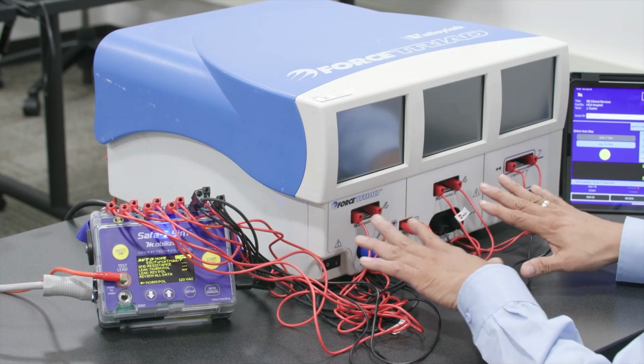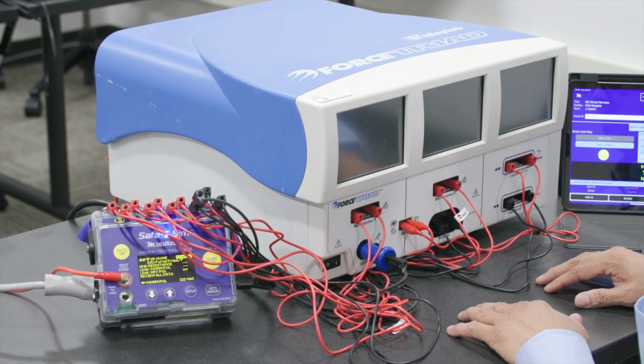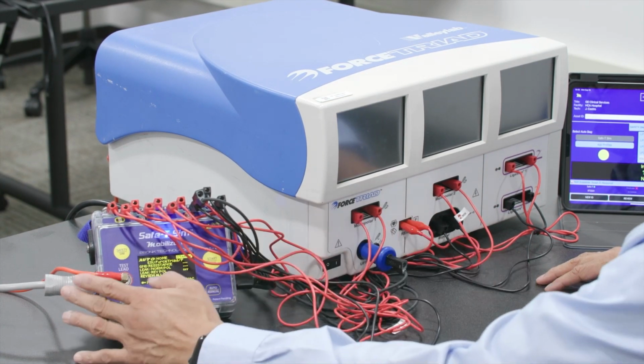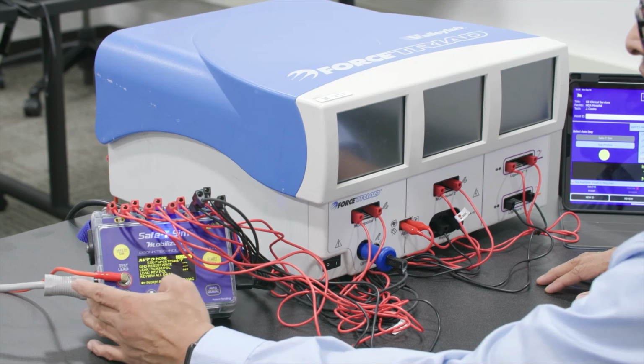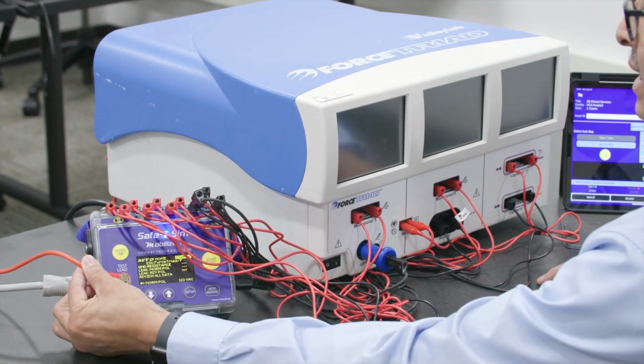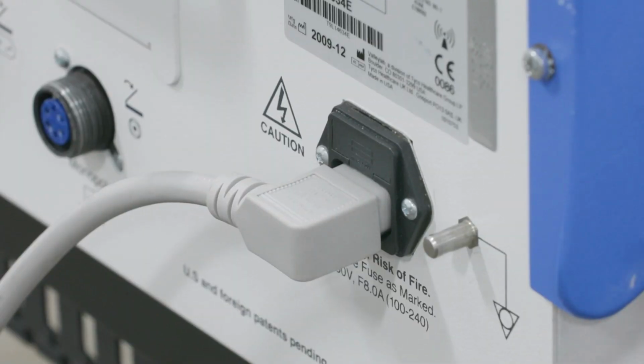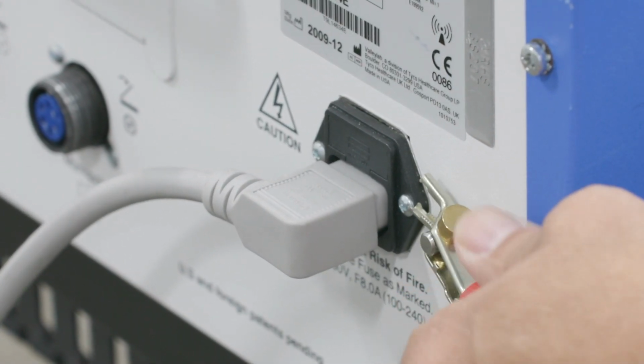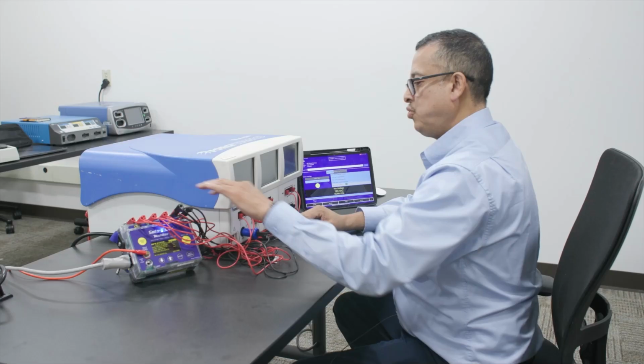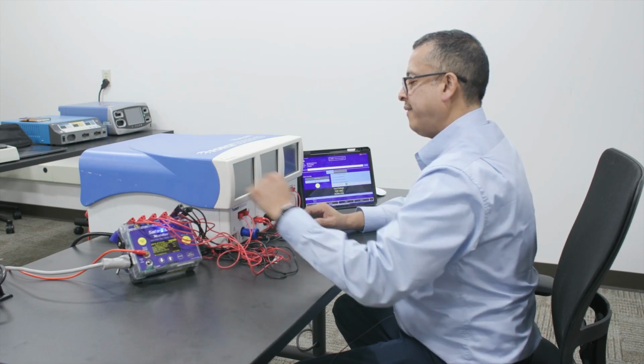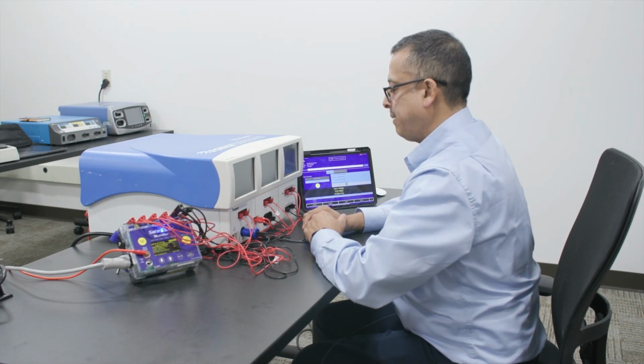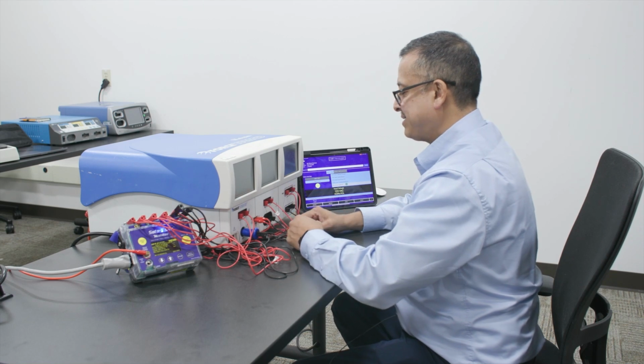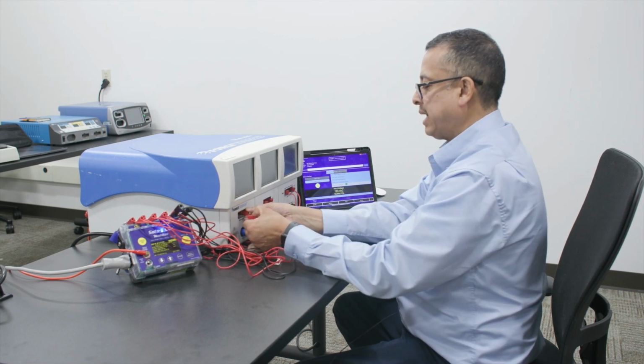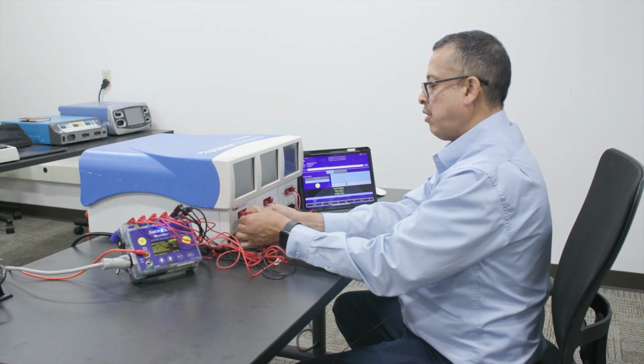Now we want to make sure to set up the unit properly. We want to do that by connecting the ESU to the left side of the safety analyzer. You have the red test lead cable that connects to the back of the unit to the ground post. And then we need to connect all of the outputs to the lead section of the safety analyzer for doing our applied parts or outputs tests. So you want to use these banana plug adapters connected to each output.